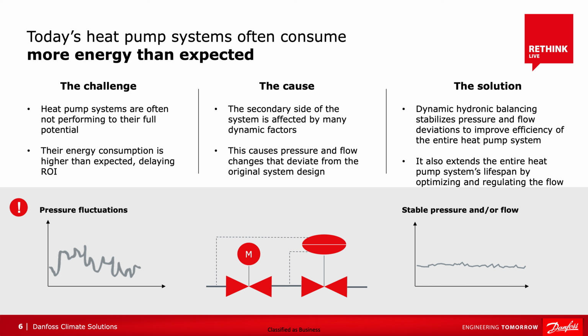Dynamic hydronic balancing valves address the root cause of unanticipated pressure fluctuations that cause system imbalances and uneven water distribution. Stabilizing the pressure and flow conditions with hydronic balancing works very similarly to a garden hose. If you took a garden hose when you were a kid and stretched it out and turned it on, water is going to flow at a set rate and a set pressure.